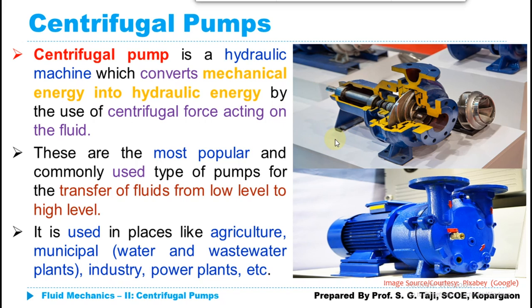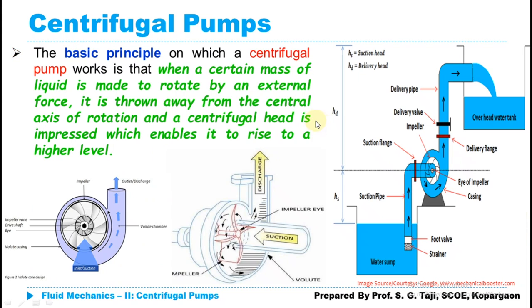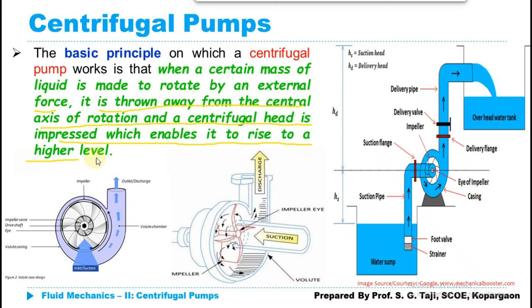The working of the centrifugal pump is based on the principle of forced vortex flow, which states that when a certain mass of liquid is made to rotate by an external force, it is thrown away from the central axis of rotation and a centrifugal head is impressed, which enables it to rise to a higher level.